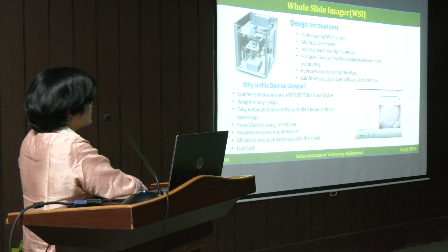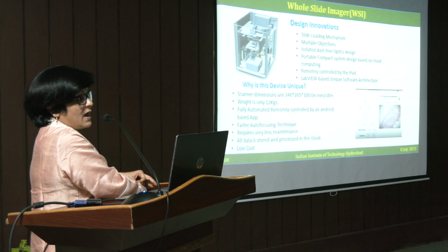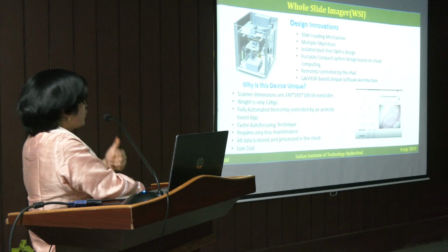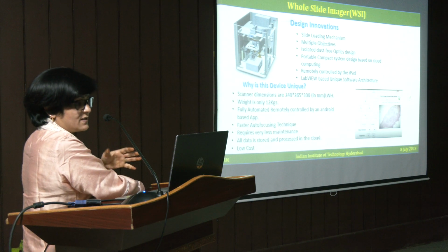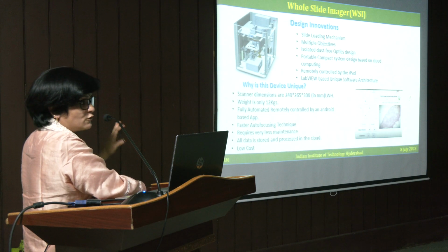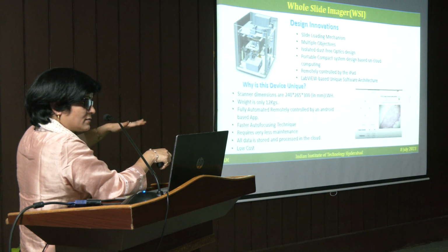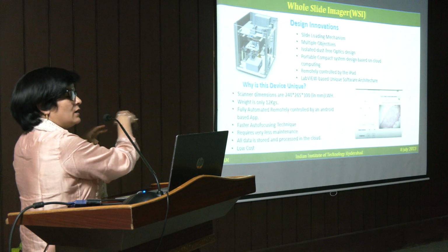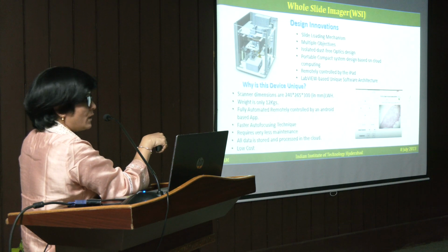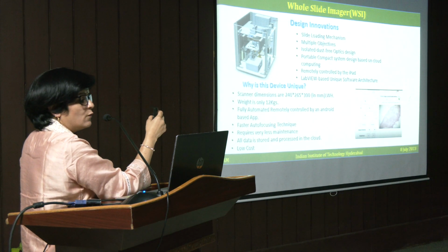The very first equipment we made was the whole slide imaging system. It is nothing but a microscope, but it does a lot of things. It has auto focusing and four objectives, and you just push in the slide and it does all the job. You don't have to focus it. Whatever slide you put in, the whole scan goes to the cloud, and doctors can sit anywhere and look at the data from anywhere in the world.